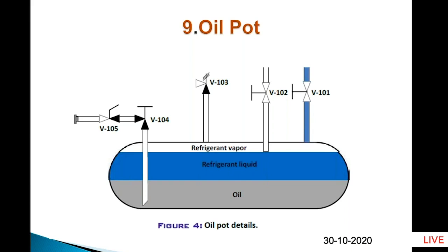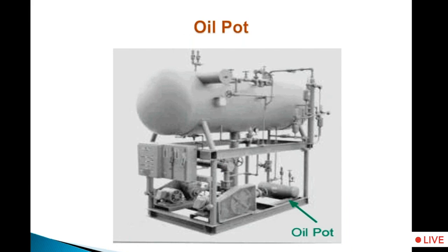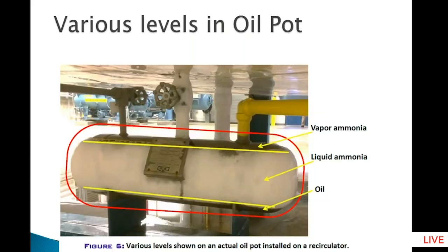Or another point, to prevent this sudden opening of a drain valve which is on each component, use a hand operated pressure relief valve, which is, when you press the handle, then only the valve opens. If you release your hand, the valve closes. Automatic shut off drain valves are available, and I use those valves on my system. So this is one of the last points which I wanted to show you.